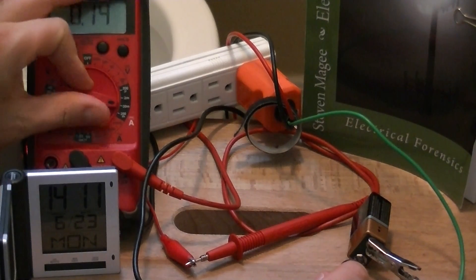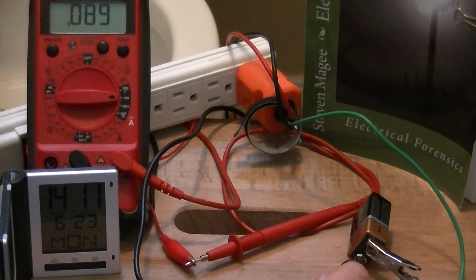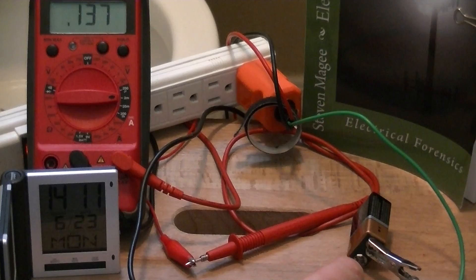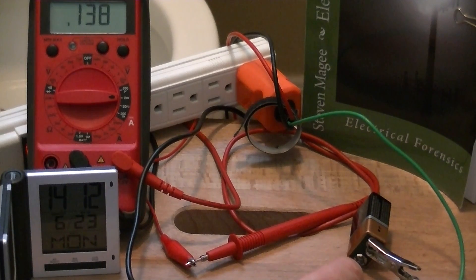Let's go down to 2 milliamps and see what we get down there. We're on the 2 milliamp DC meter range. And you can see that we're getting 0.138 out to the garden. That's 138 microamps that were passing through the toilet drain.